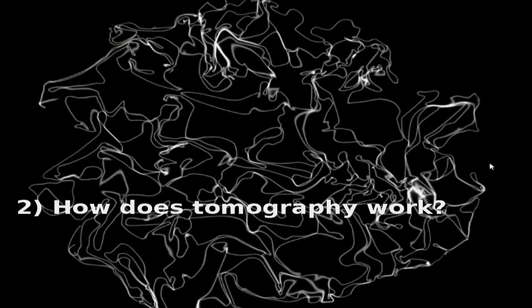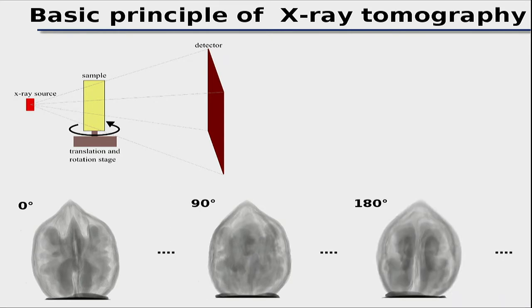Now let's discuss how tomography actually works. The machine takes many radiograms over 360° of rotation — the more images, the better the quality. It assembles a 3D volume where each voxel corresponds to the attenuation coefficient at that point in space. The software to do this reconstruction comes with the machine; you don't need to program it yourself.